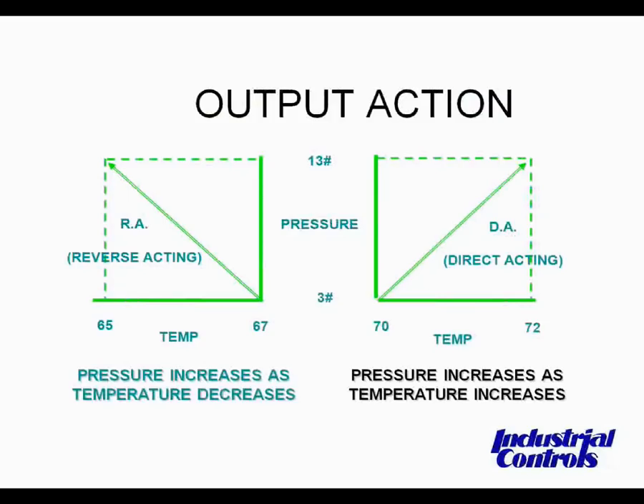In selecting a thermostat, if the action is not known, typically we work backwards from the final control device fail position and the action needed. For example, in the chart on the right side, if we knew that a normally open valve was being used for heating, we would apply a direct-acting thermostat. Therefore, as the temperature of the room increased, we would want the output pressure of the thermostat to increase and therefore close the valve. So a direct-acting thermostat in a heating application with a normally open valve would give us the result and action that we desired.